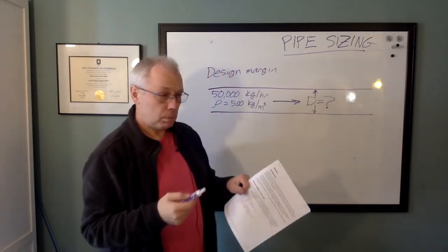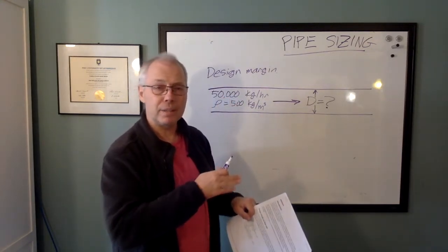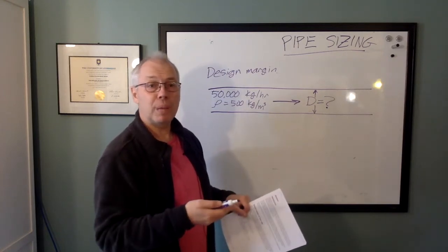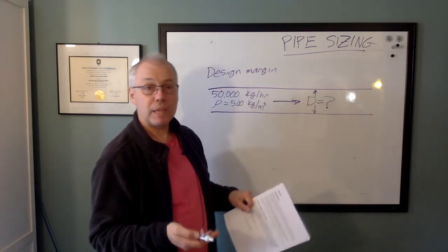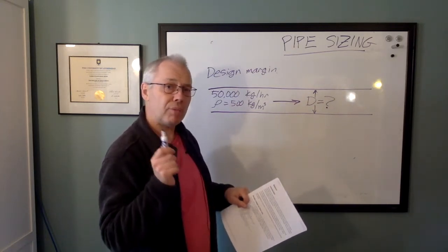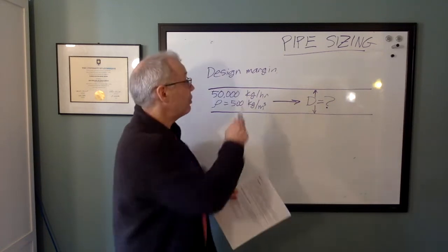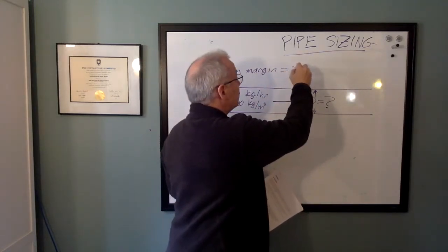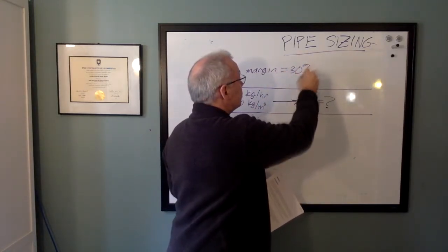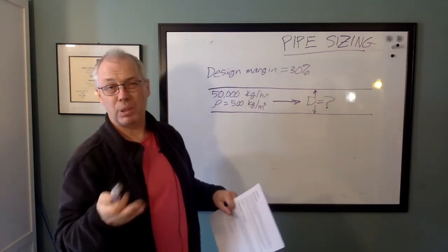So what sort of design margin do we need? We could size our piping for 50,000 kilograms an hour, and it will work fine today. But five years from now, when the plant manager says, let's increase the throughput of the plant by 30%, your perfectly good pipe may not be big enough. So we always have to consider a bit of design margin. In our case, we'll consider 30%. So we don't have a flow rate of 50,000, it's 50,000 plus 30%.